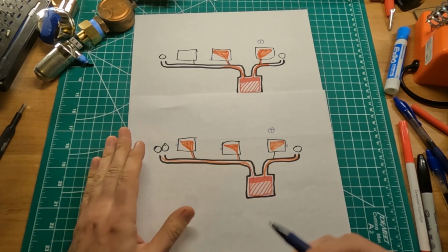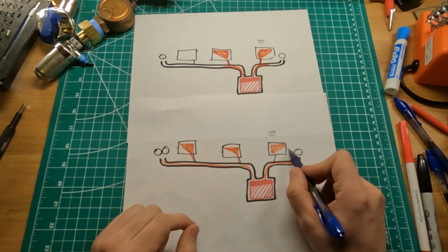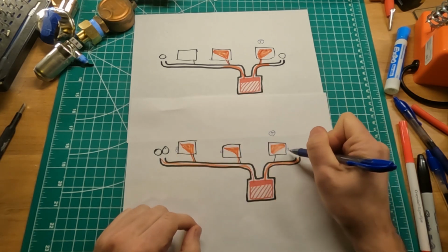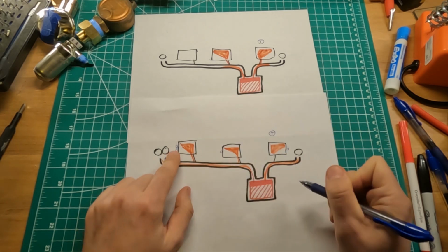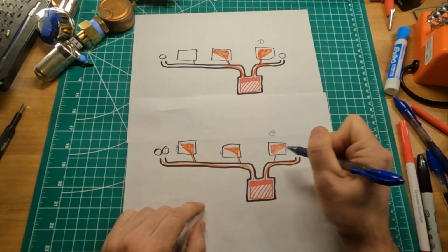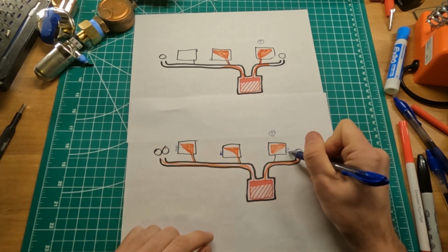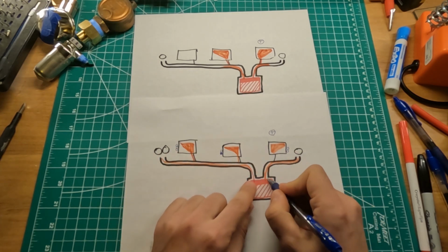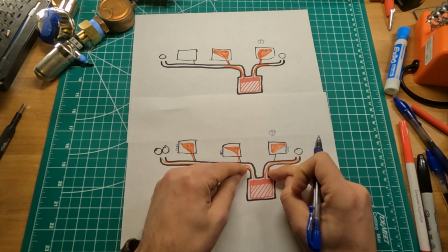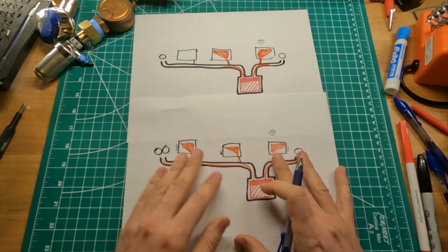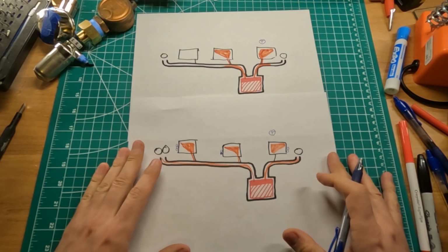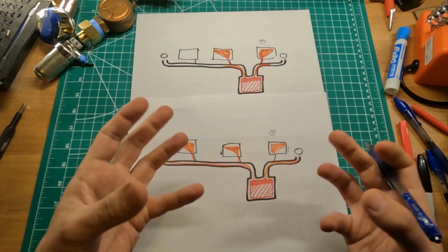So in other words, sometimes when we hear about balancing the steam, we keep on talking about just, oh yeah, let me just increase, let's say, the venting here, and maybe let's make it triple dots here, and then maybe 2 dots here, or even 1 dot here, and then maybe 2 dots here. And yes, that can work if we're talking about a system that keeps on producing a constant amount of steam. What ends up happening, depending of course on the situation and the temperature outside, is that much of the heating often happens in the early stages. Let's say when the boiler just starts producing the steam, and there's a limited amount of steam happening.